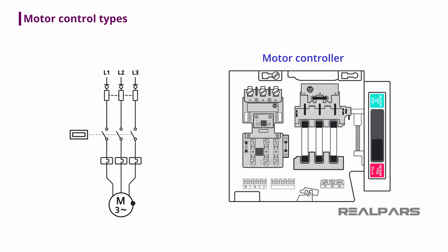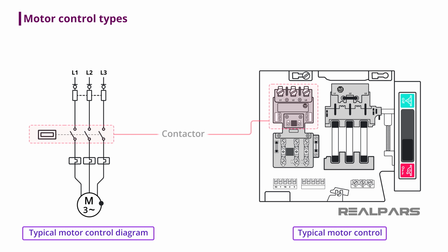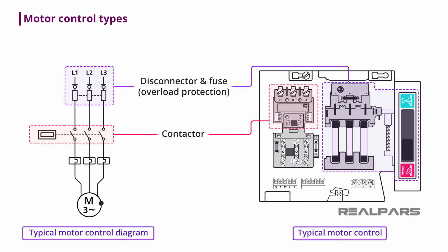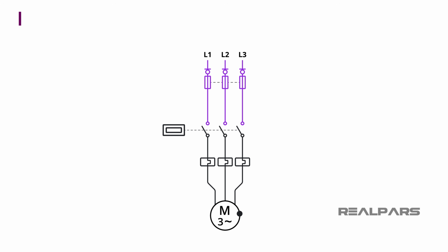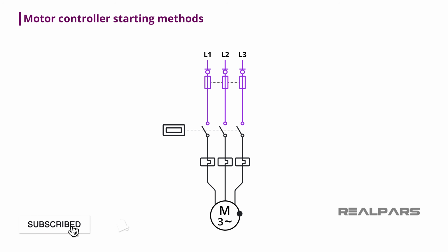Motor controllers are also referred to as motor starters. These devices are most often offered in a single unit with circuit disconnecting means, a contactor or other type of motor actuator, circuit overload protection, and motor overload protection. Motor controllers can be grouped by starting method and by starter type. Motor controllers can be classified by starting method.